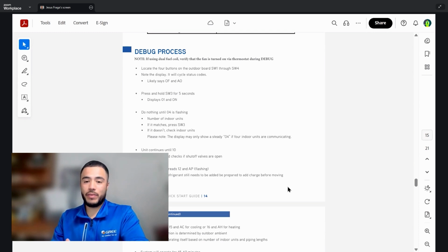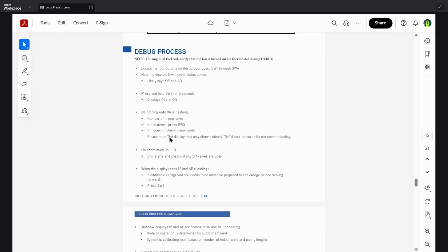Usually when you get an error code, it means that there's something that went on with the installation, whether it's communication wire, whether it's maybe power to the indoor units, and so on and so forth. So just depending on what kind of error code you're getting at the outdoor unit will indicate what is actually wrong with the system. And once all those errors are corrected, if you have any, you should be able to easily go through this debug process and have the system fully operational within 40 to 45 minutes.